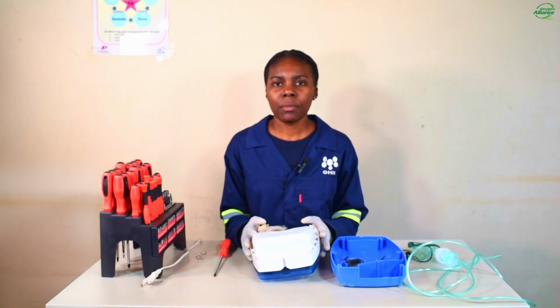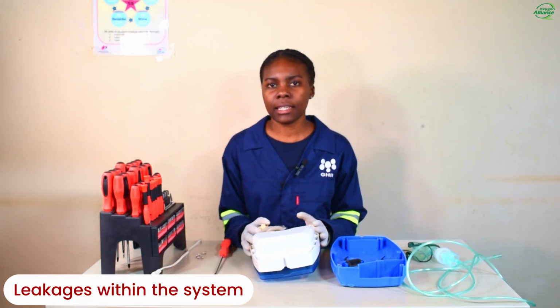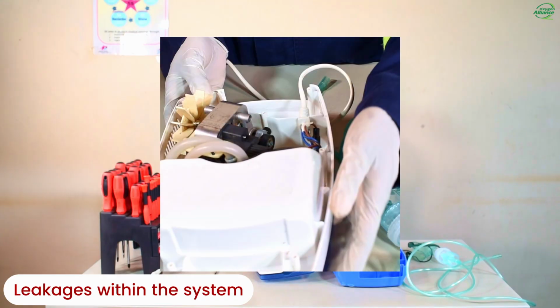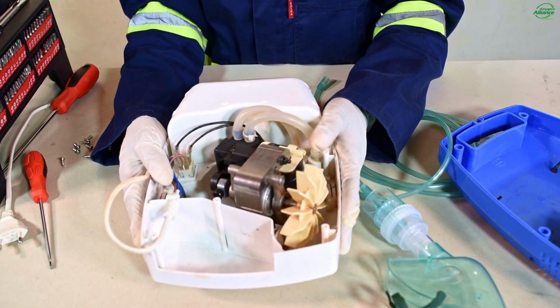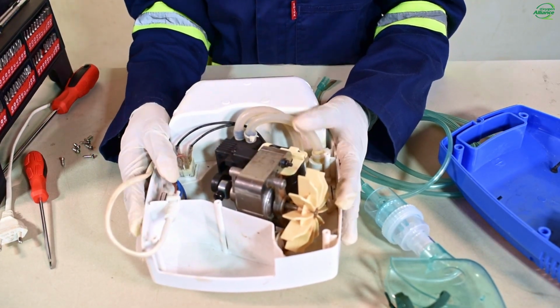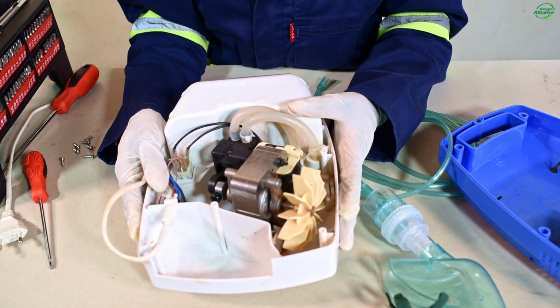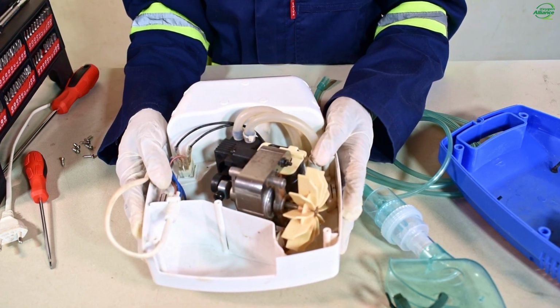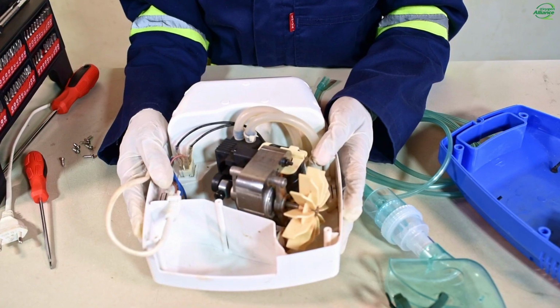Another cause of no mist production is leakages within the system. Leaks in the system reduce air pressure before it reaches the medication, resulting in reduced or no mist.